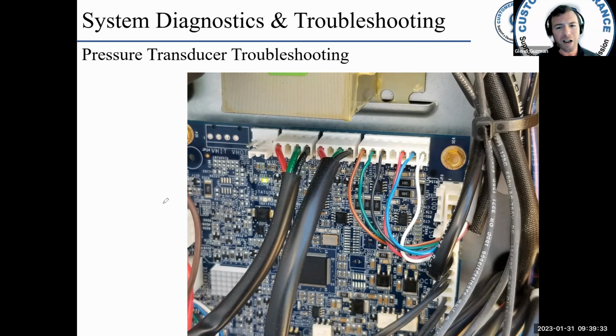Okay. Now, I will tell you, this can get a little tricky because the software in the board assigns the transducer. Okay, so I guess it's kind of hard to explain without actually showing you, but let's say I had two transducers. One of them read 100 PSIG and the other one read 300 PSIG. Okay, once I plug those into the board, it's going to say, hey, the one that's reading 100, that's suction, and the other one is discharge.